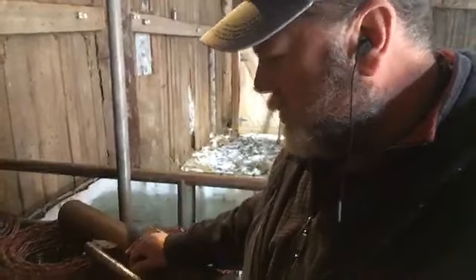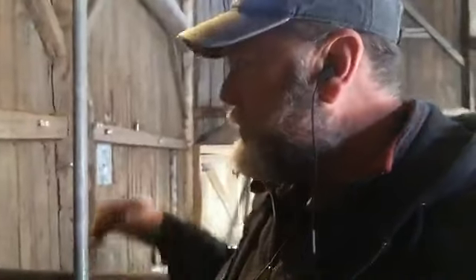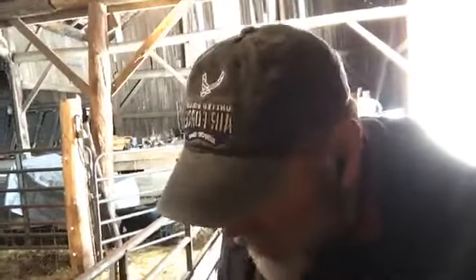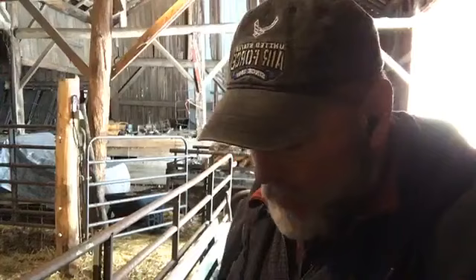I wanted to show here — you can see I had to drive a ground post right there. That was just a piece of stainless steel pipe I had laying around, happened to be about six feet long, so I drove that down. Now it's in the barn — generally you want to drive it into ground that is a little bit moist, but you don't want the ground post to corrode because that will change the conductivity. Stainless steel always works well, conducts electricity really well, and it won't corrode.